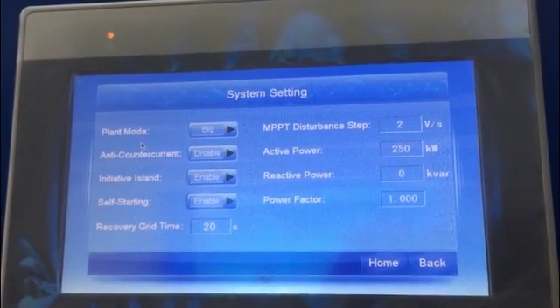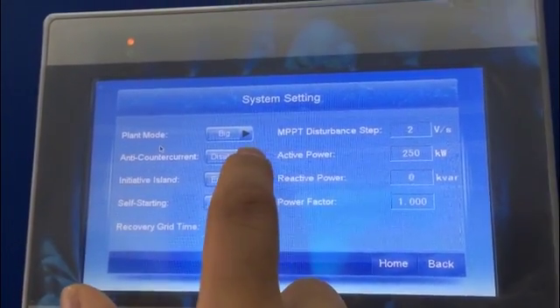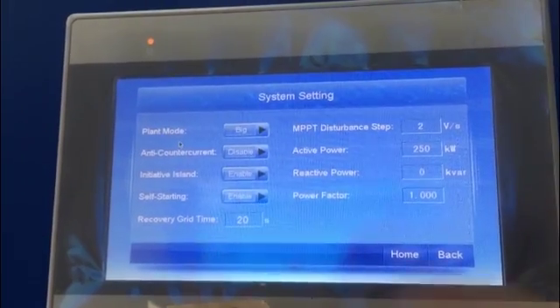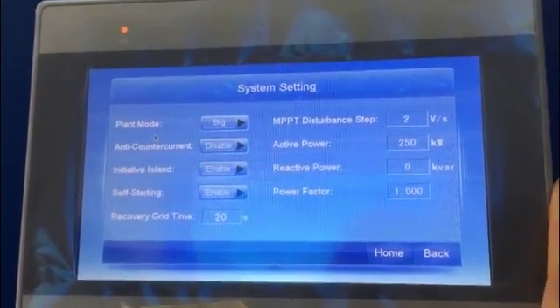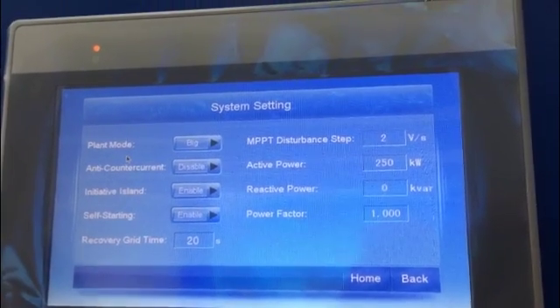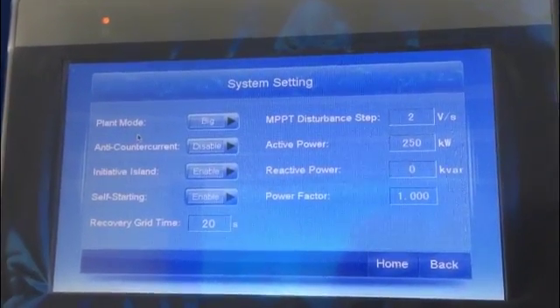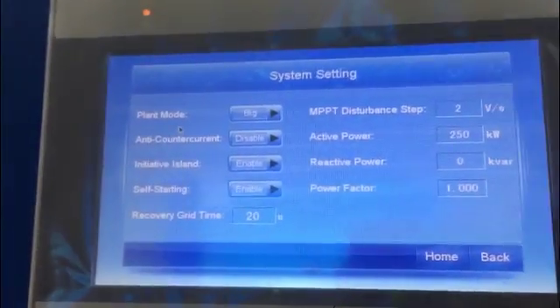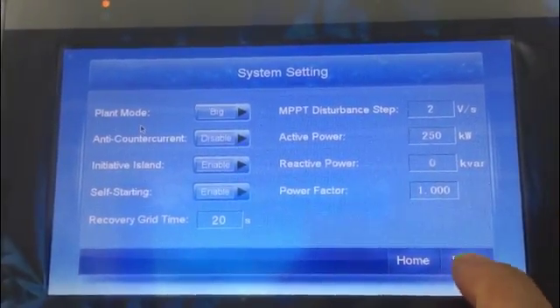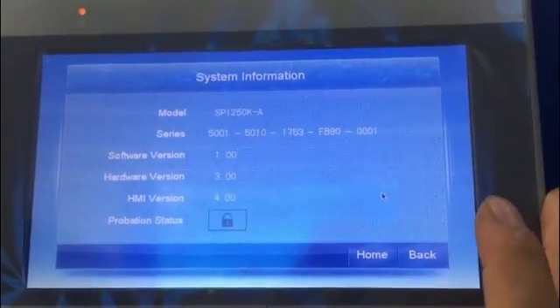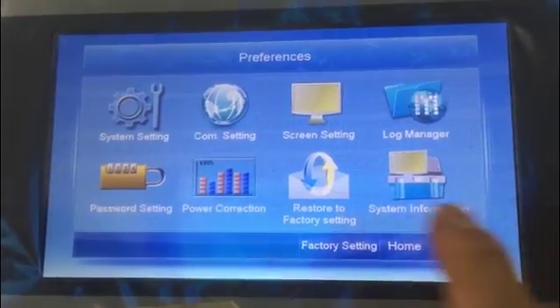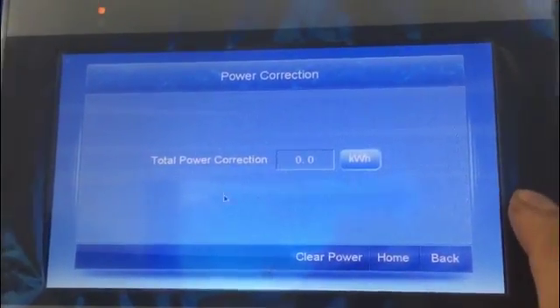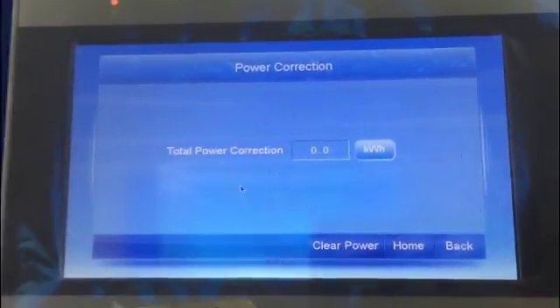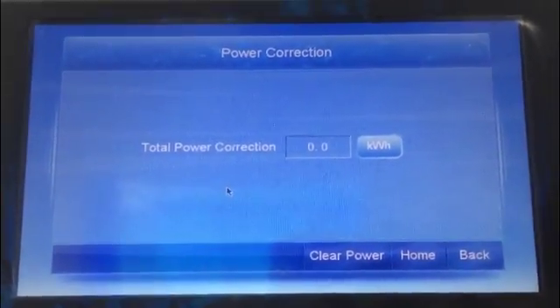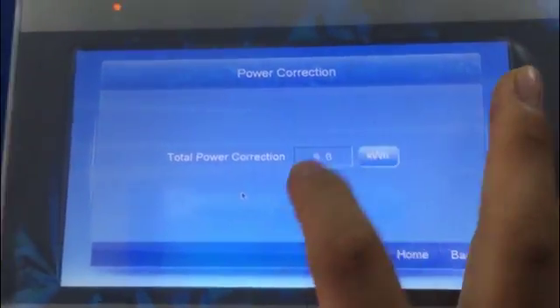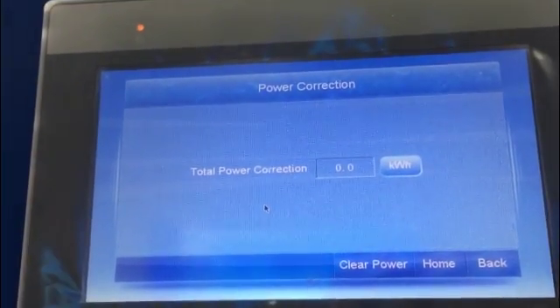And for performance, you can set the MPPT disturbing step, active power output, and the power factors. It's pretty similar to the energy storage, but there's a lot of difference. Also, the unit has a total power correction function, which is settable on the touch screen with specific readings you'd like the system to be.